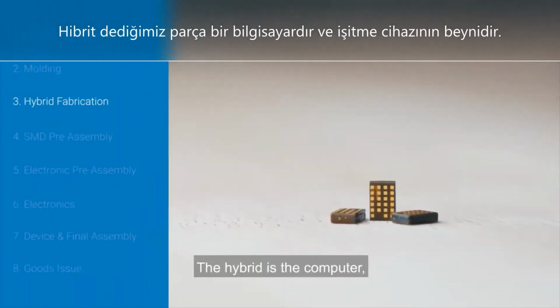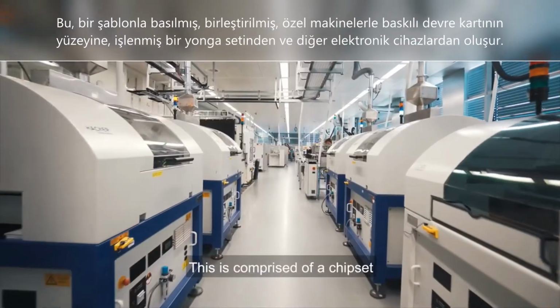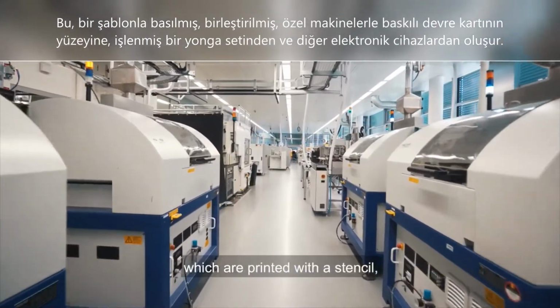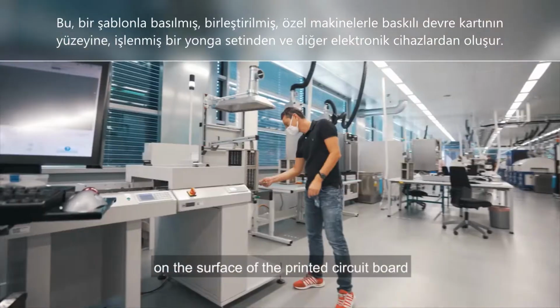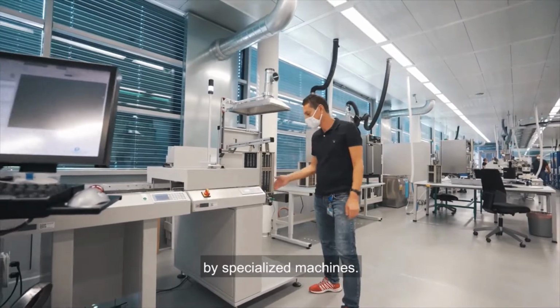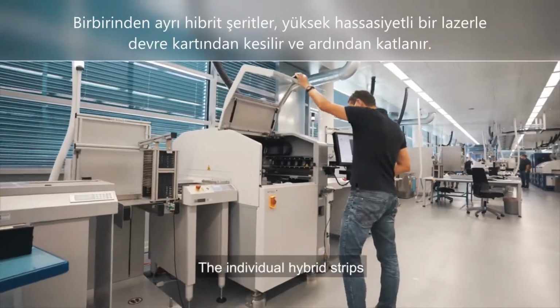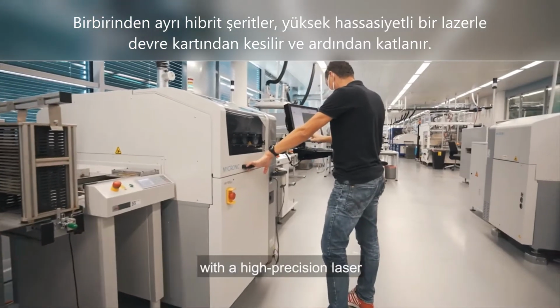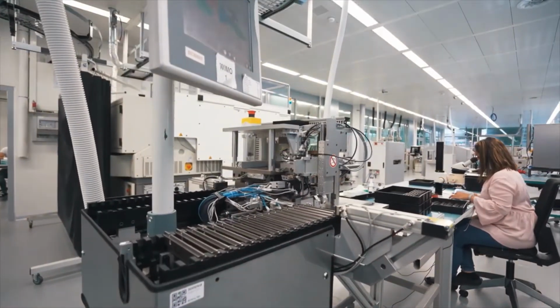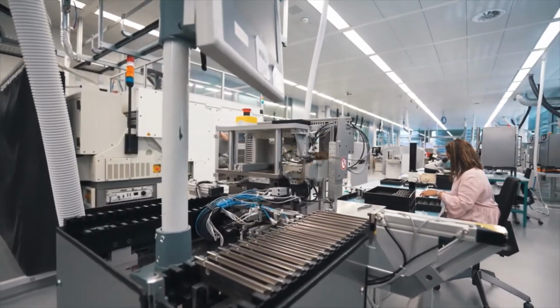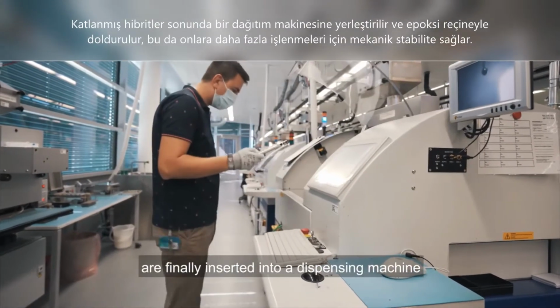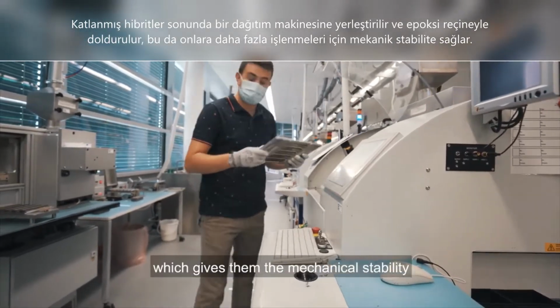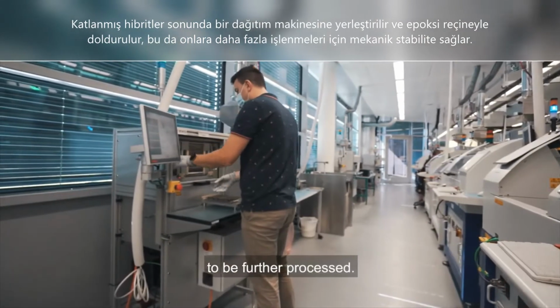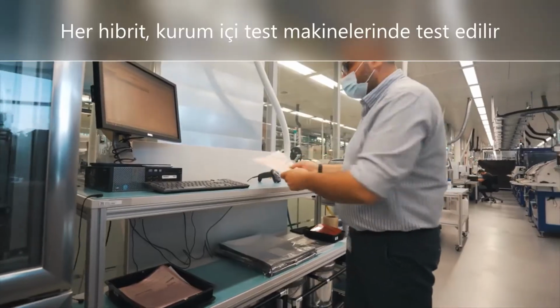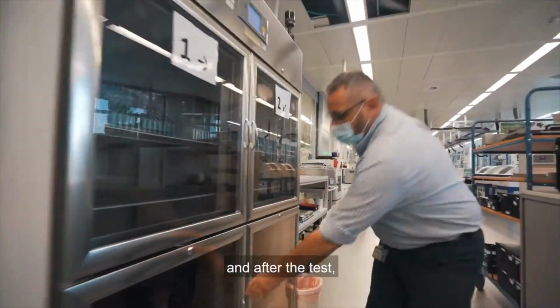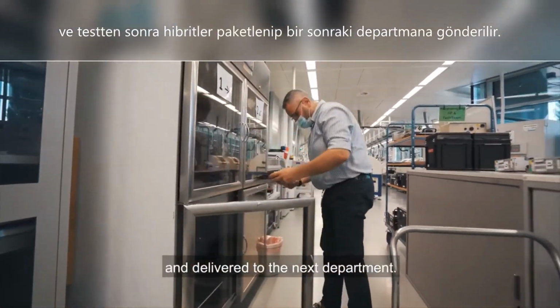The hybrid is the computer, the brain of the hearing aid. This is comprised of a chipset and other electronics which are printed with a stencil, assembled, soldered and underfilled on the surface of the printed circuit board by specialized machines. The individual hybrid strips are cut out from the circuit board with a high-precision laser and then folded. The folded hybrids are finally inserted into a dispensing machine and filled with epoxy resin which gives them the mechanical stability to be further processed. Every hybrid is tested through in-house testing machines, and after the test, the hybrids are packed into a tape and delivered to the next department.